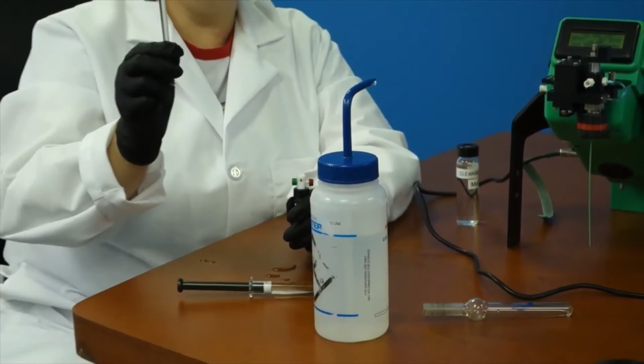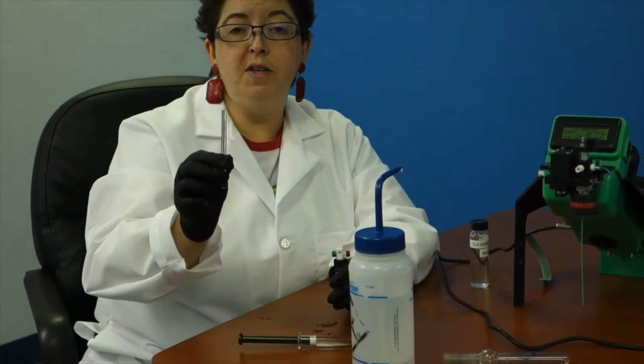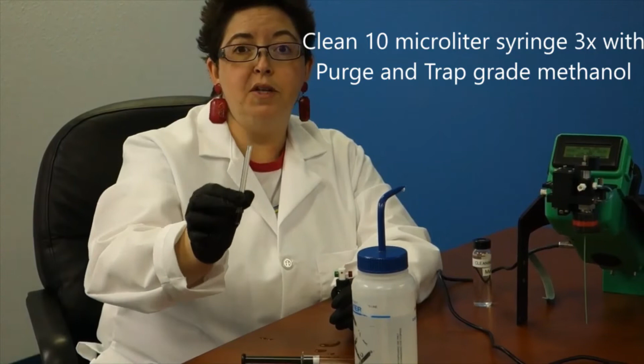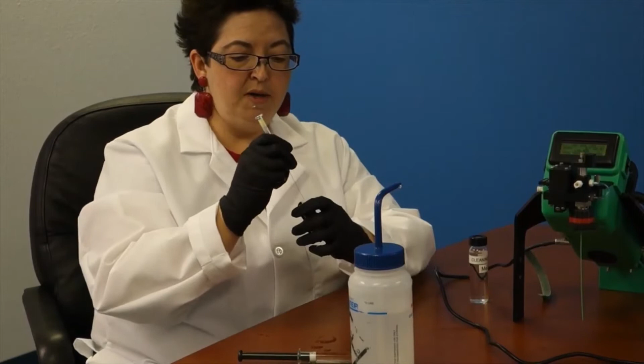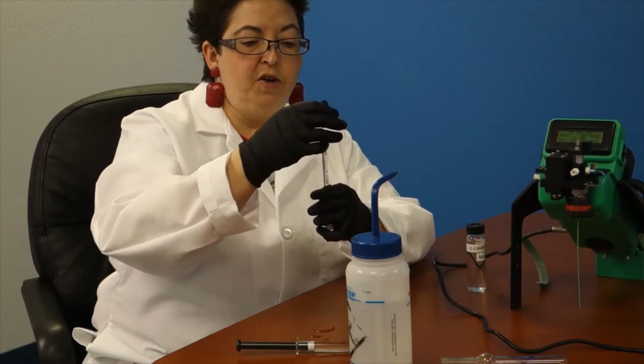Okay. This is a 10 microliter syringe. We like to get ours from Hamilton. The first thing you want to do is clean this out 3 times with methanol, and then you want to prime it. Okay, so this has been cleaned 3 times with purge and trap grade methanol. Okay, to prime it, with a smaller syringe like this 10 microliter, I just fill it up and dump it out. Now I'm going to pop it back in. Okay. Folks, if you're not comfortable with the use of these microliter syringes, we do have a link to a video that covers that in detail.